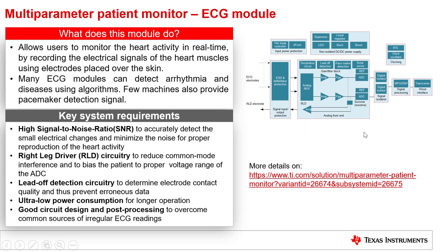Let's start with the ECG module. This module allows users to monitor the heart activity in real time by recording the electrical signals of the heart muscles using electrodes placed over the skin. The key system requirements for the ECG module are: high signal-to-noise ratio, or SNR, to accurately detect the small electrical changes and minimize noise for proper reproduction of the heart activity; and RLD, or right leg driver circuitry, to reduce common mode interference and to bias the patient to the proper voltage range of the ADC.